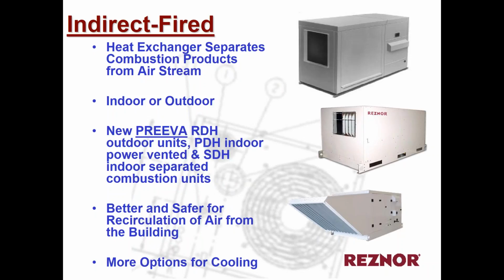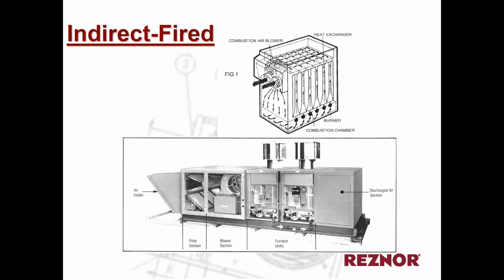And then once again, going through the indirect fired, it is that unit that has a heat exchanger that separates the combustion products from the airstream. And this is probably the larger part of what we do as far as makeup air product. This will also show you we make products that could be used for makeup air that have separated combustion furnaces, duct furnaces. And you can see them there in parallel as they go, or in series as they go, installed in the larger commercial products.